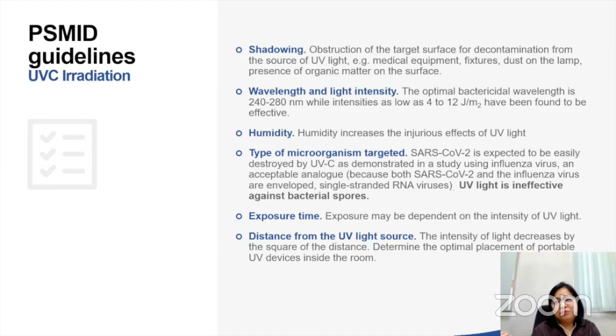The exposure time is also very important. It is dependent on the intensity of the UV light. And the farther an equipment or a surface is from the UV light source, the more the intensity of the light decreases. So that means the sterilization will also be suboptimal.